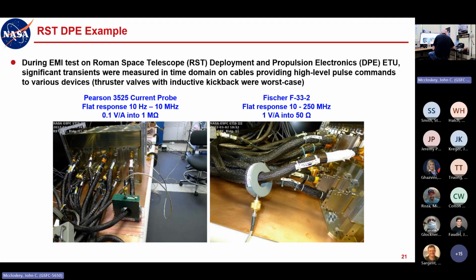So the significance of the flat response is that when you're doing a frequency-based test, like a frequency swept test, the flat response is not terribly important. You're taking into account the current probe's transfer impedance as a function of frequency, and that's entered into your software. It does those conversions for you, and the response basically just is what it is. But when you're doing time domain measurements, having a flat frequency response is very important, because then it's providing the same characteristic, the same transfer function or transfer impedance, to all of the frequency components contributing to the waveform.